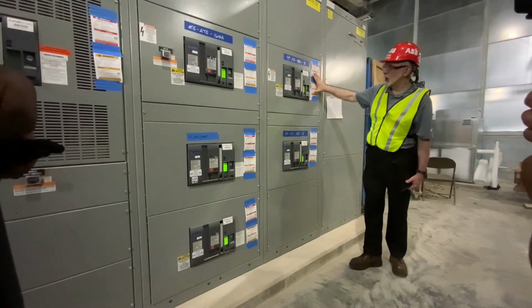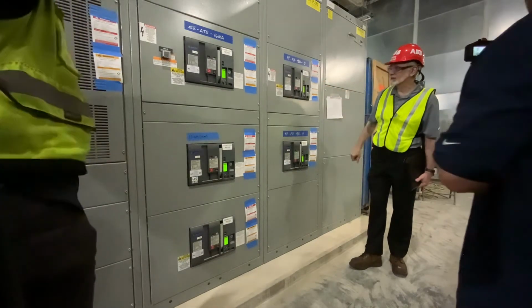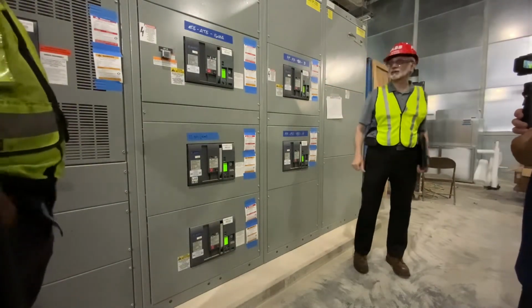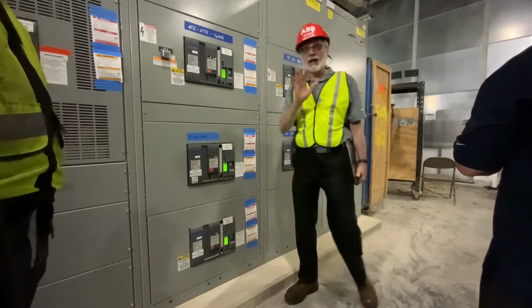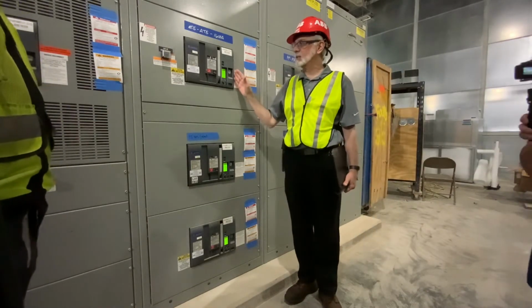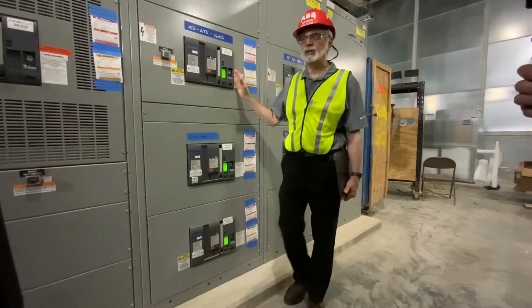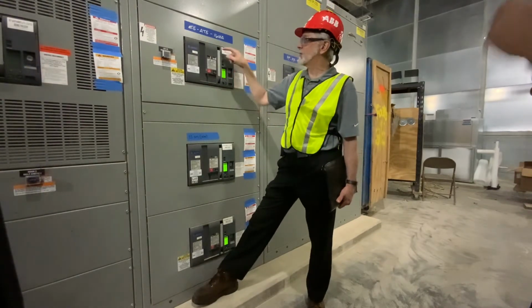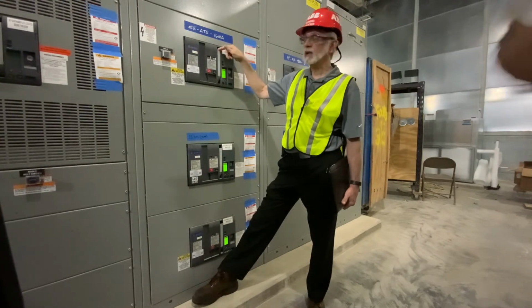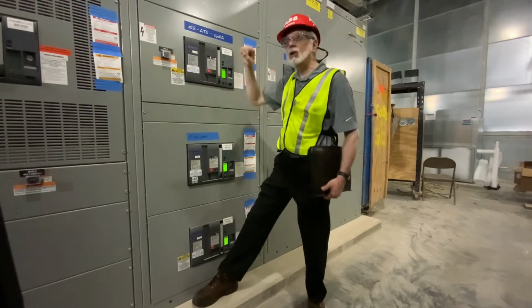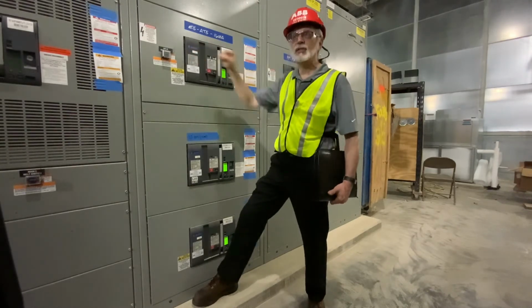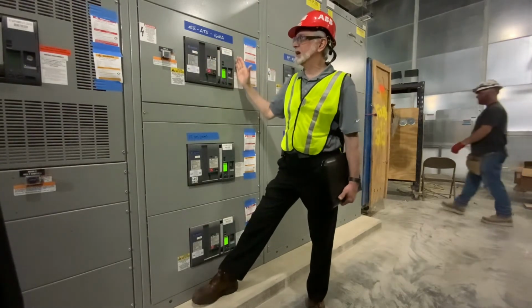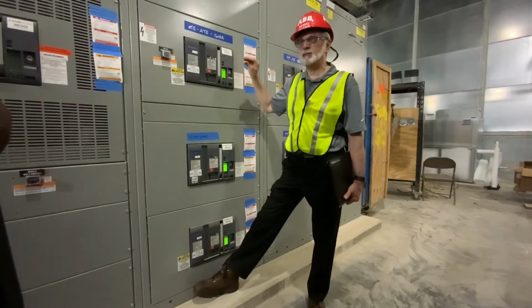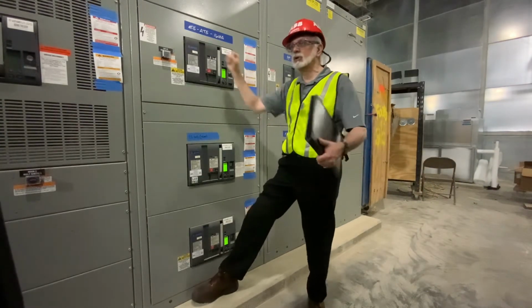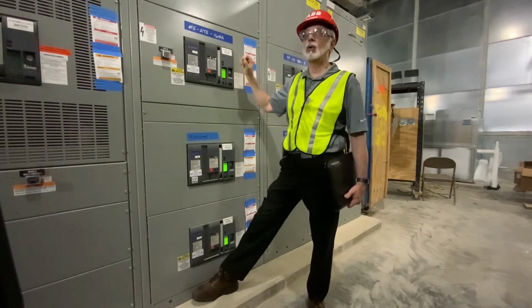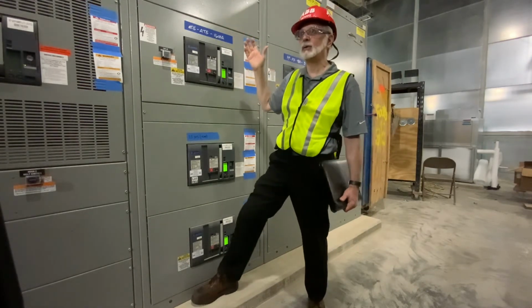This is going to a large power panel, and the section going on to those power panels right over there. Yeah, probably. The way you operate these breakers is, as you might think, these are what we call stored energy breakers. So the way that you operate them is, you can see there's a little handle here. On smaller breakers, you have like a toggle, okay? You can throw that with mechanical energy. Because these breakers are so large, they have springs inside them, because two small boys, a dog, and a lever wouldn't be able to throw this breaker, okay?